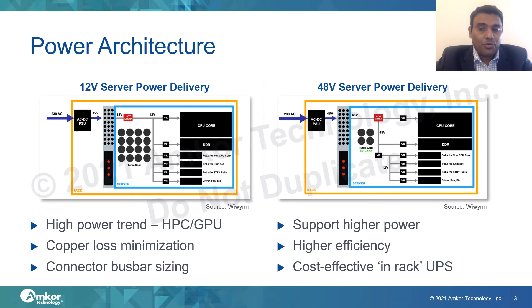The benefits at the rack level are obvious, given the reduction in busbar sizing, number of capacitors, and lower copper losses. However, the challenge remains how to achieve voltage conversion from 48 volt to the server board. To power the CPU cores and DDR memory blocks, traditionally less than 1.8 volt is required.